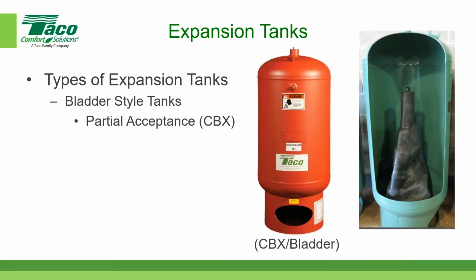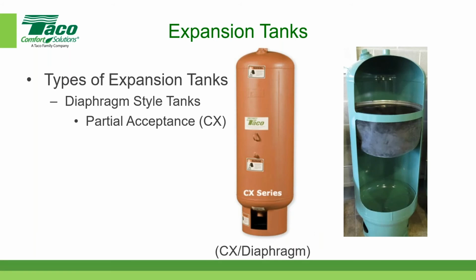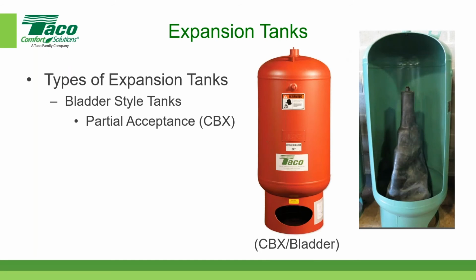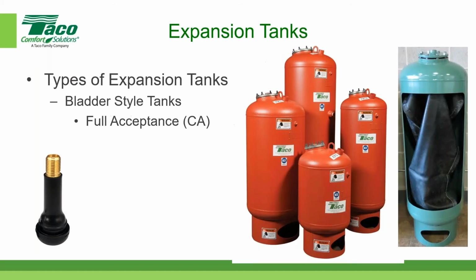The partial acceptance is a little bit less expensive, and the diaphragm is the least expensive. The diaphragm cannot be repaired, so if it should fail, you have to replace the whole tank. The partial acceptance, depending on the model, you can get a partial acceptance with a replaceable bladder, in which case, if the bladder should fail, you can replace it. And same thing holds true with this model, the full acceptance, you can replace the bladder.